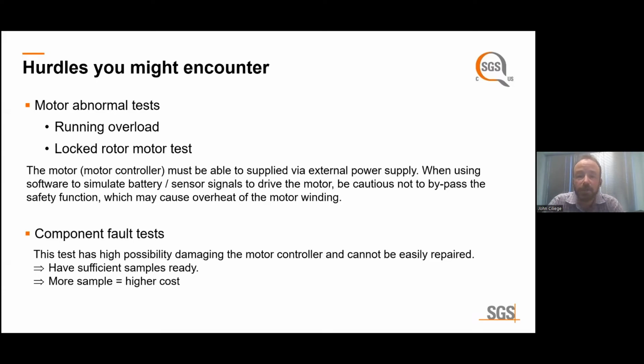So just some other things that come into play when doing testing. There are many destructive tests in UL 2849. Some damage the unit, and this is acceptable as long as it doesn't lead to electric shock or fire hazard. For example, running an overload test or a locked rotor test on the motor. Again, we may damage the product, and that's okay.